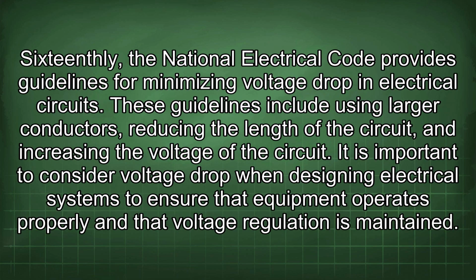16thly, the National Electrical Code provides guidelines for minimizing voltage drop in electrical circuits. These guidelines include using larger conductors, reducing the length of the circuit, and increasing the voltage of the circuit. It is important to consider voltage drop when designing electrical systems to ensure that equipment operates properly and that voltage regulation is maintained.